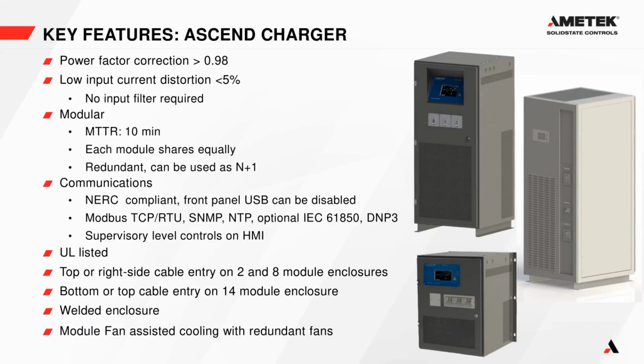So some of the key features of Ascend: it's a power factor corrected input charger, so our power factor is above 0.98. We have low input current distortion, less than 5%, and we can achieve that without an input filter. It's also a modular charger, so the mean time to repair is 10 minutes or less. In most cases, that'll just be swapping out a module.